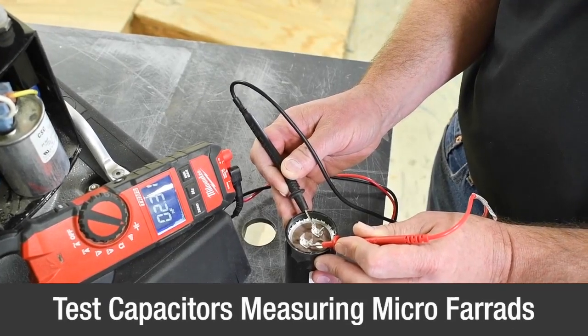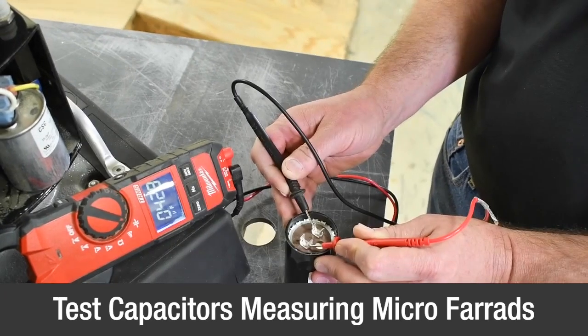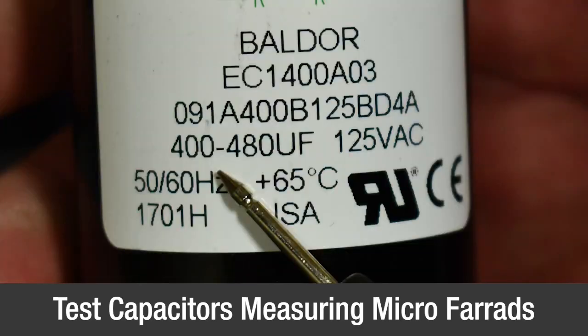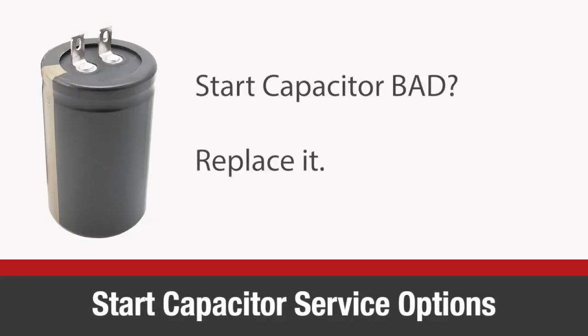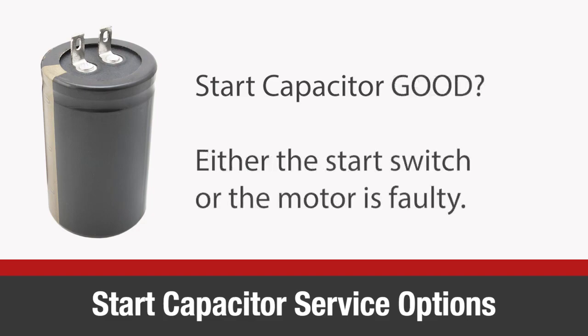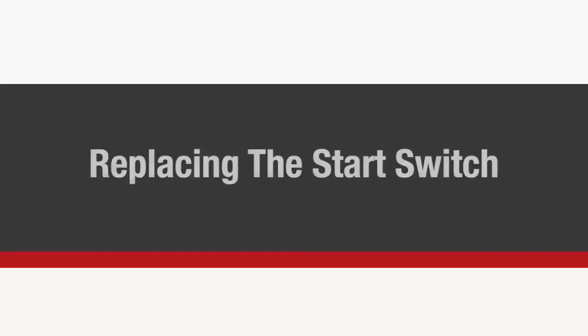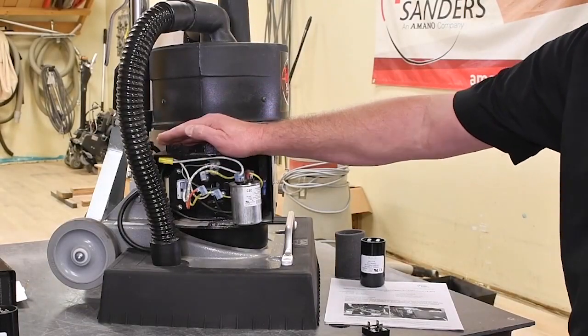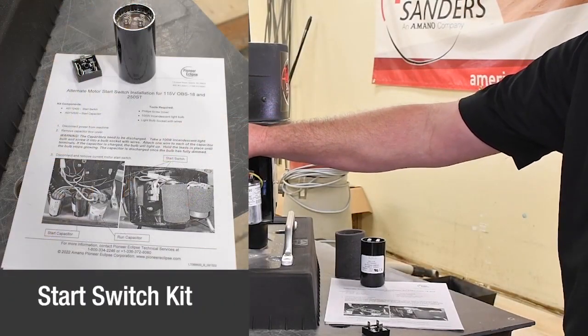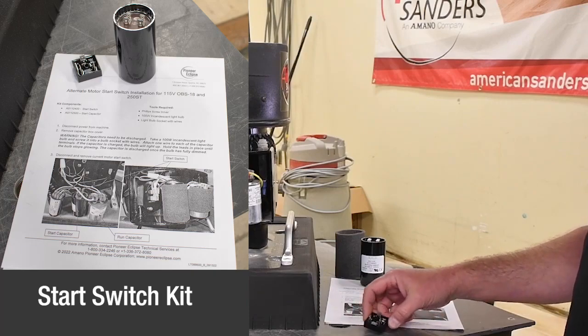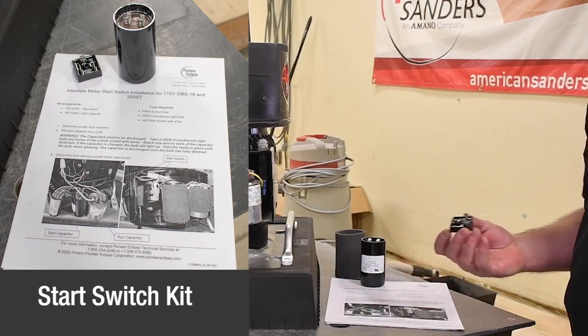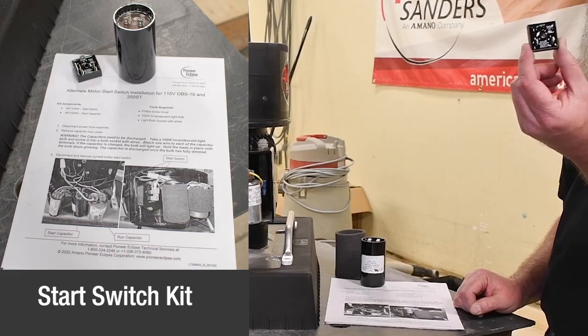Test the capacitors with a meter that measures microfarads. The label on the capacitor will show the range of microfarads for the unit. If the start capacitor is bad, replace it with a new capacitor from American Sanders. If the start capacitor is good, either the start switch or the motor is faulty. Replacing the start switch. Replacement start switches for the OBS 18 come as a kit with a new style start switch along with a new start capacitor that is a microfarads rating matched to the new switch. Installation instructions are included.